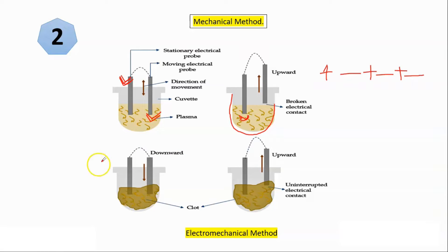So connection is like this: one time connection established, other time breaks, again establish, again break, again establish, again break. But as soon as clot is formed, will the firm clot allow the movement of this free electrode or probe? No, answer is no because clot engages it inside and does not allow the motion or oscillatory motion.